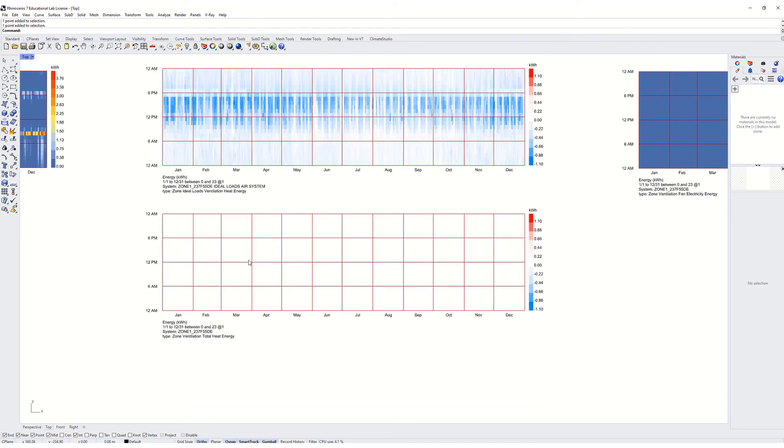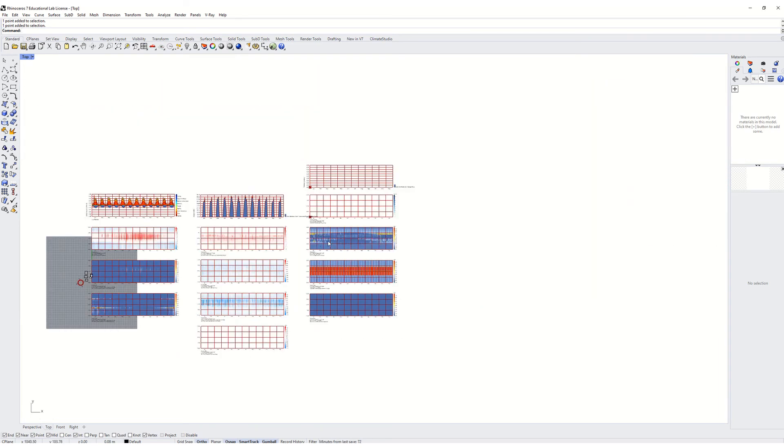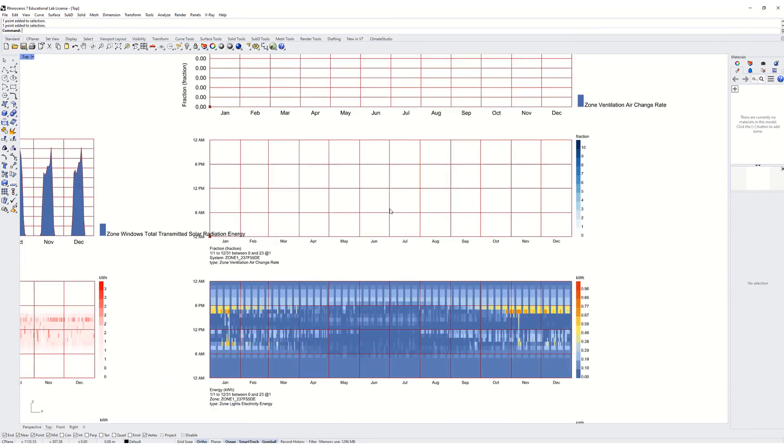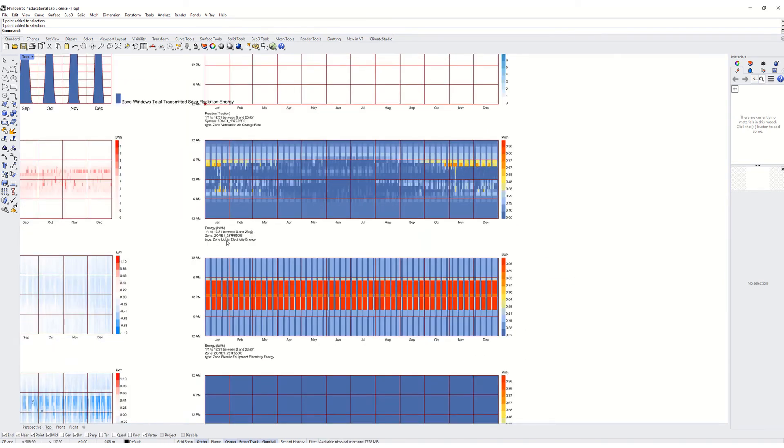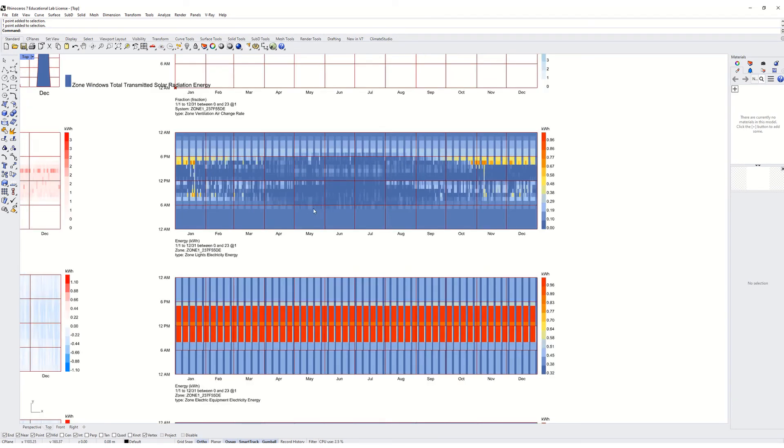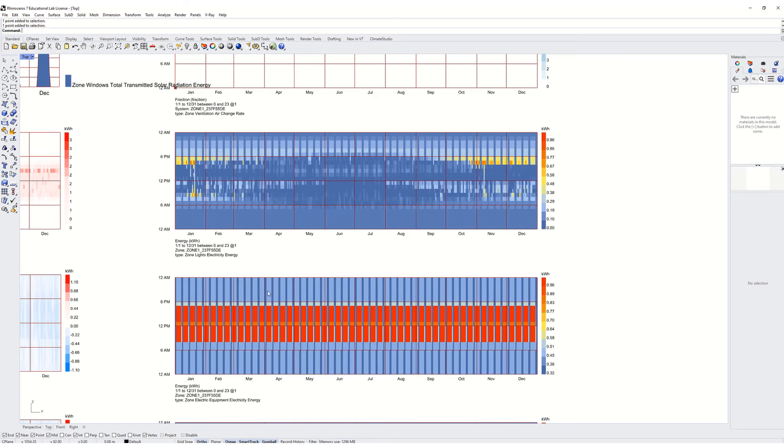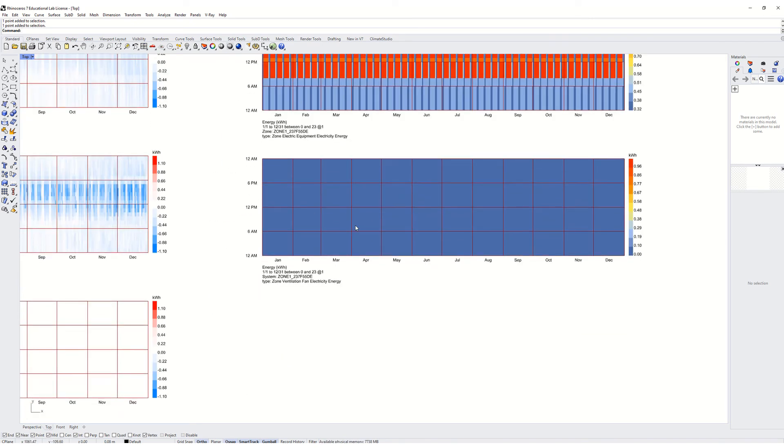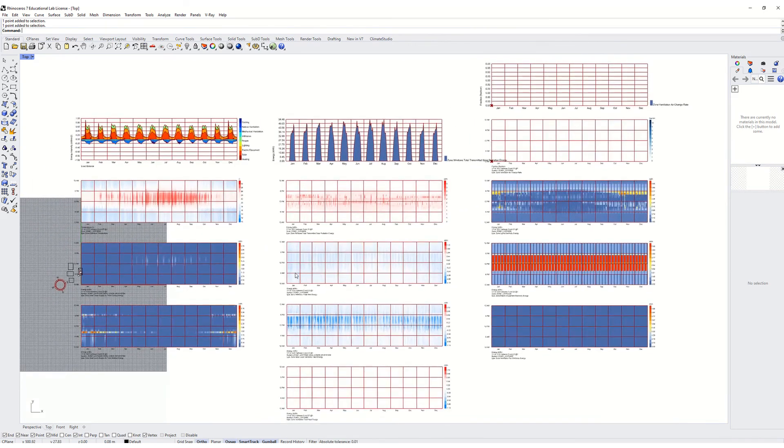Here we've got infiltration and ventilation losses. And that's from the economizer. And then this is from natural ventilation. And then over here, we've got the ventilation air change rates, which are zero. In this particular case, we've got lighting electricity. So now check this out. Whereas before, it almost looked like a piano keyboard with so much lighting energy used during the daytime. Now almost all of that daytime use is blue, meaning zero energy is being used because the lights are turned off when they're not required. That's our daylight dimming that we just looked at. Then there's the equipment and the fan energy. So that's kind of an overview of these graphs.